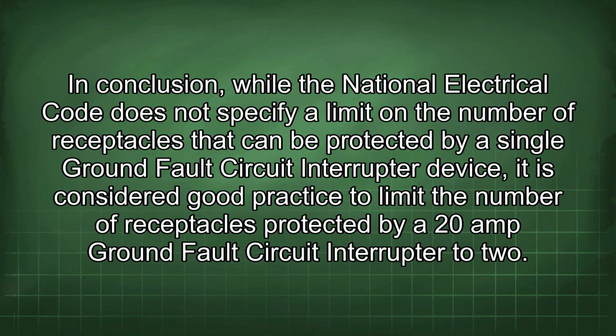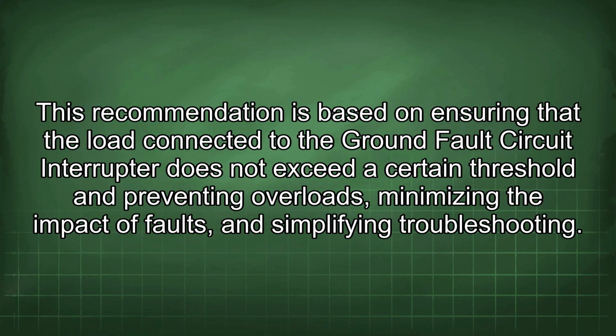In conclusion, while the National Electrical Code does not specify a limit on the number of receptacles that can be protected by a single ground fault circuit interrupter device, it is considered good practice to limit the number of receptacles protected by a 20-amp ground fault circuit interrupter to 2. This recommendation is based on ensuring that the load connected to the ground fault circuit interrupter does not exceed a certain threshold and preventing overloads, minimizing the impact of faults, and simplifying troubleshooting.